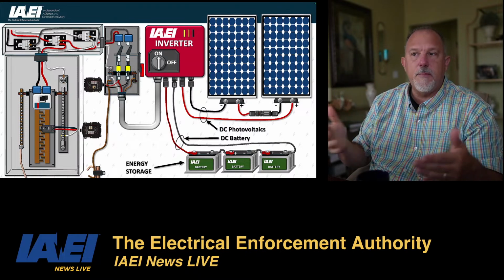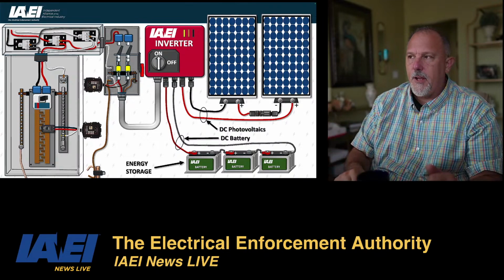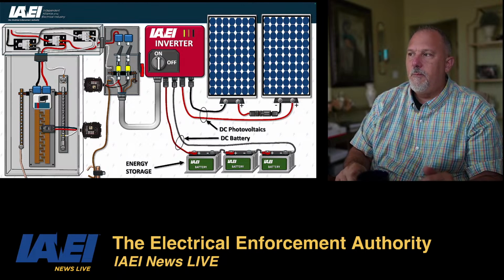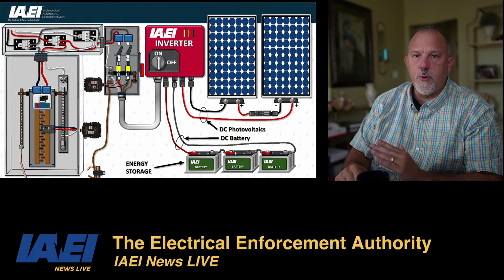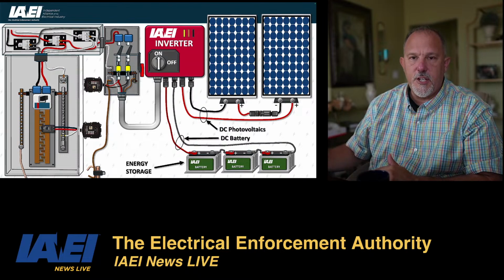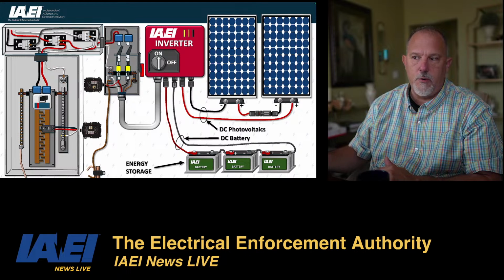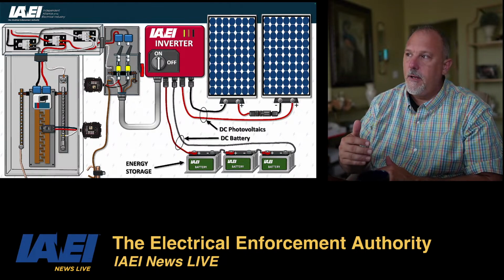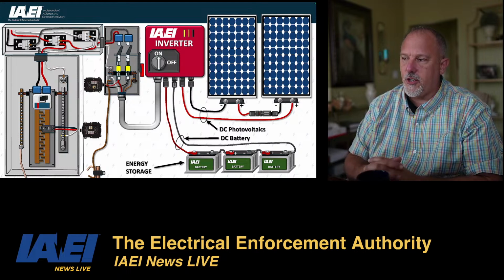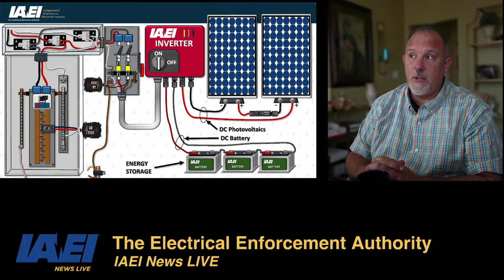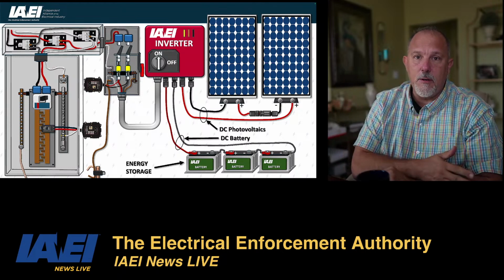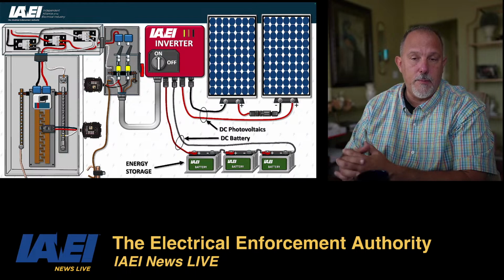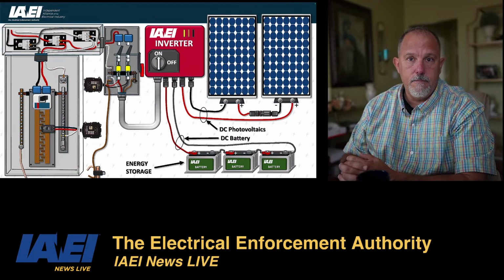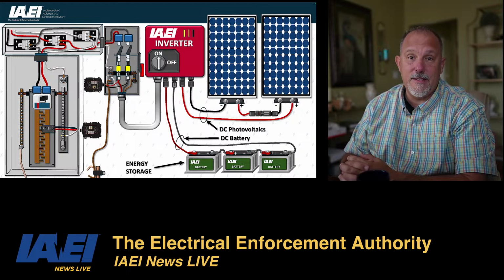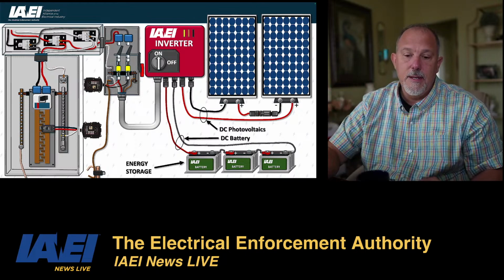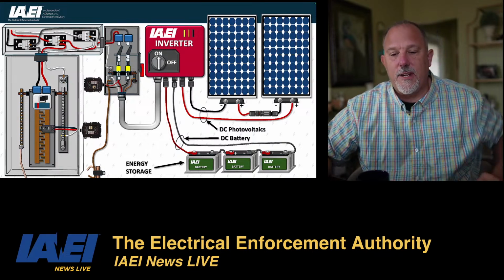Any excess, it could supply power to the normal loads whenever there was utility power. But for the most part, the energy storage system was a backup to a backup. Say it was a diesel generator and the generator ran out of fuel, then you ran off of batteries, and the solar panels would charge the batteries. But in those cases, I lost the utility, and I have to supply power, so I need a standalone system capability. These systems can be complicated, but fun to try to understand.